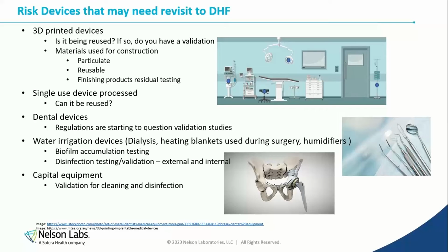So something that you want to think about for your design history file, keep it open and say, okay, I think this can be reusable. Let's test it 3 or 4 times and say, I have the data that it can be reused 3 or 4 times. Now your device can be used for that many times and not thrown away.